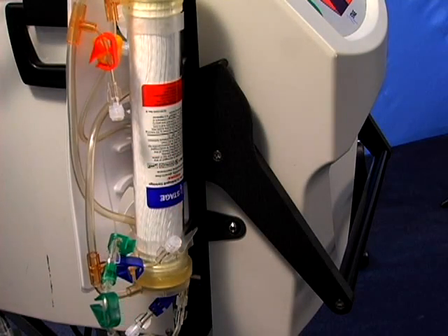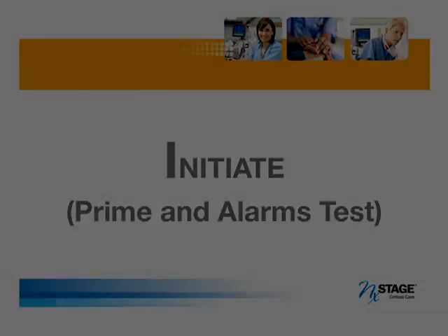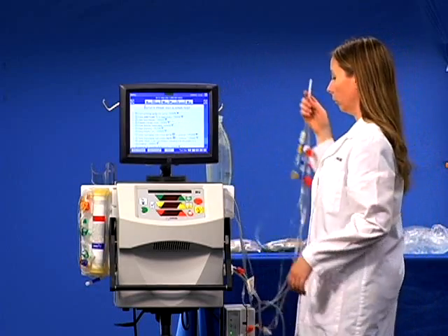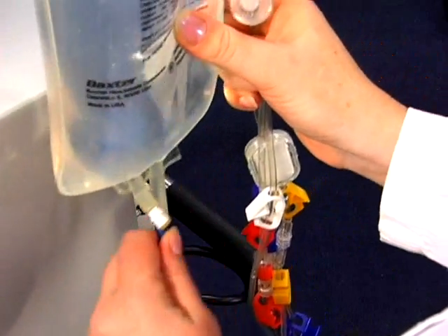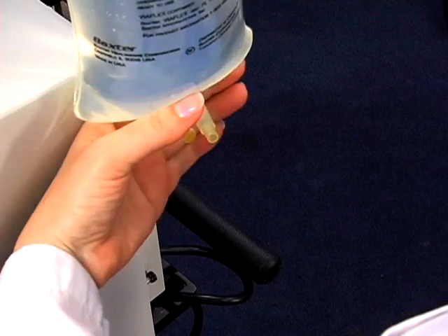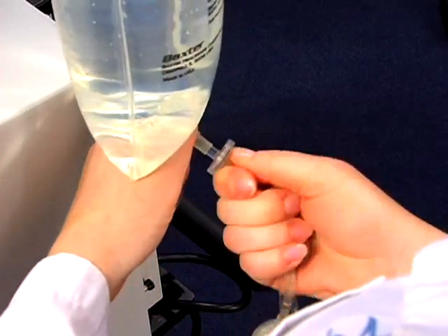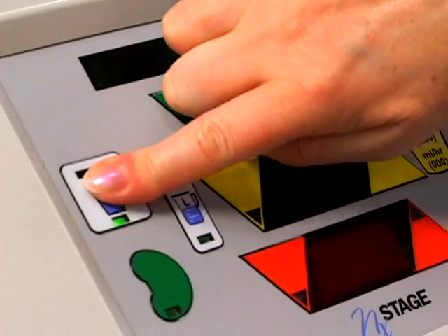You are finished with setup. Click on the initiate button. Insert the priming spike into one liter of normal saline until the saline bag is flush with the disc on the priming spike. Press the add fluid key to begin prime.